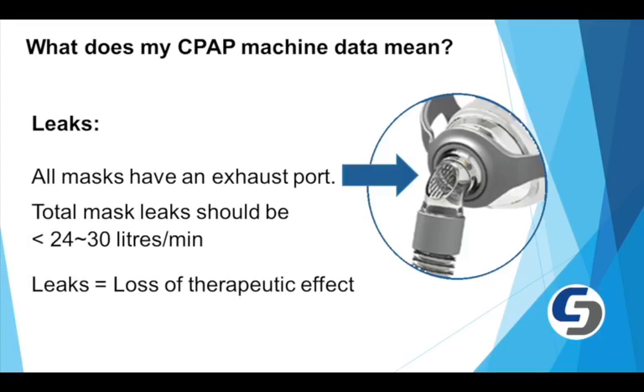So an intentional mask leak is a design feature of every mask so that the patient's carbon dioxide from the breathing can be expelled safely. Auto machines will try to compensate for leaks by automatically increasing the pressure to maintain an adequate treatment pressure. In some cases, this can be undesirable. For example, the pressure will be too strong and wake the patient up, or a stronger pressure actually forces the lips and mouth open. So if a patient is using a nasal or nasal pillow mask and then opens their mouth, then this will be considered to be an undesirable leak.